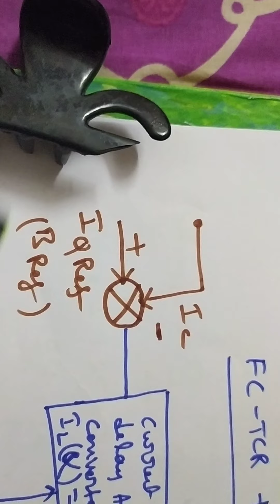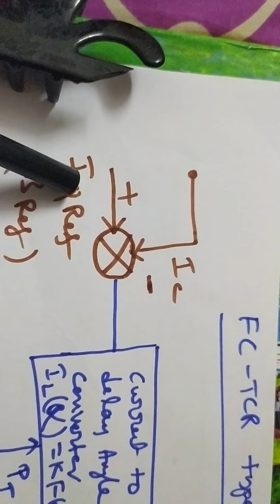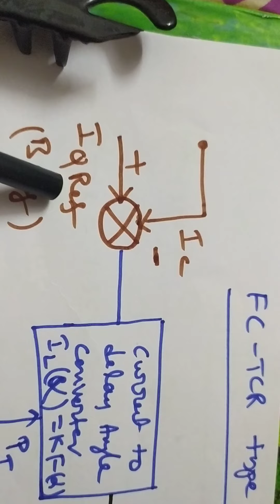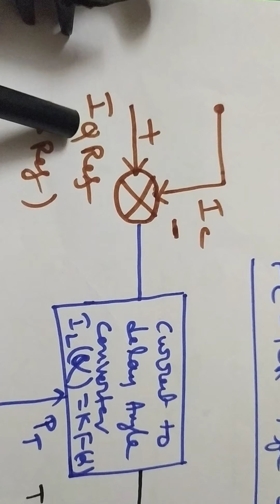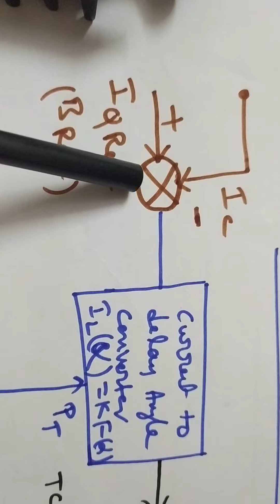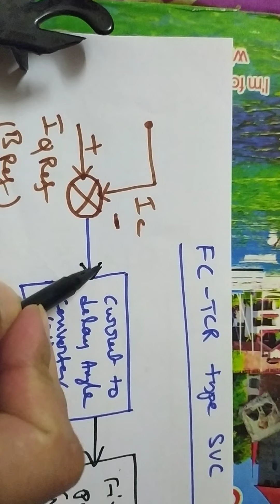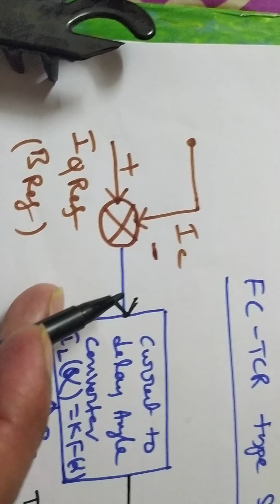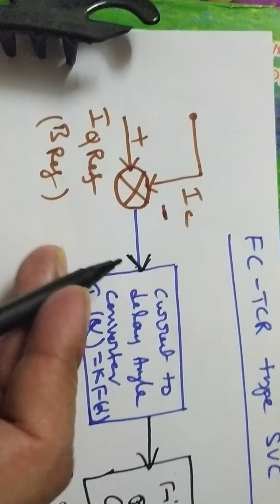In the control circuit, the very first one is IC, the capacitive current, and IQ reference, the reference reactive current or reference susceptance B reference, given to a summer or comparator. The comparator will generate the deviation between IQ reference and IC, so you will get the required reactive current from this loop. This is one of the functions of your control circuit. The required current from the SVC is obtained from here.